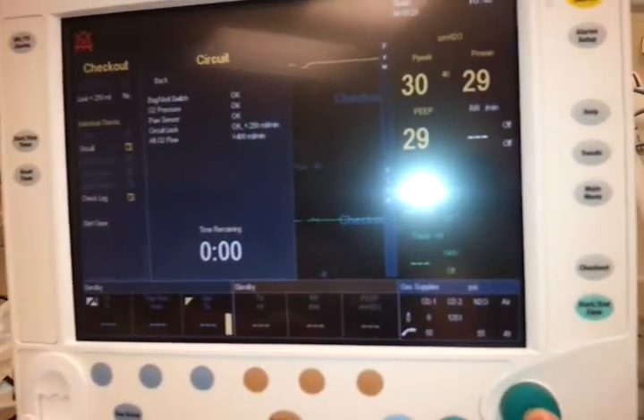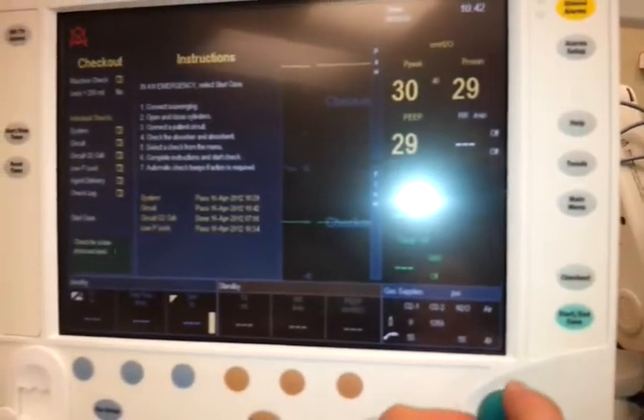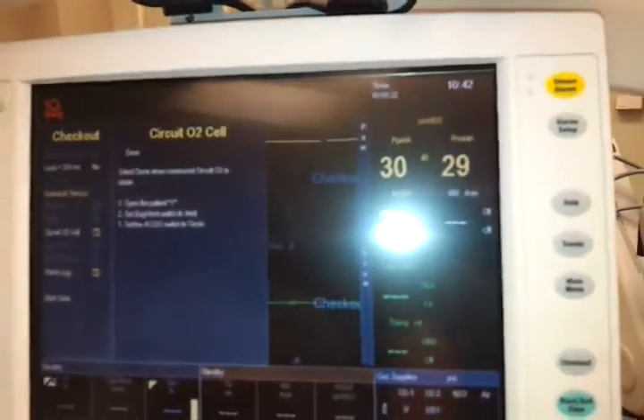Okay, so circuit test is done, everything passed. Now you have to do your circuit O2 cell. So you hit that. You want to open the patient Y. So just leave it open to atmosphere, and you want it to switch to vent. Basically, you're looking for the FiO2 to drop to about 21-22%. So it's going down. We have to give it a second.